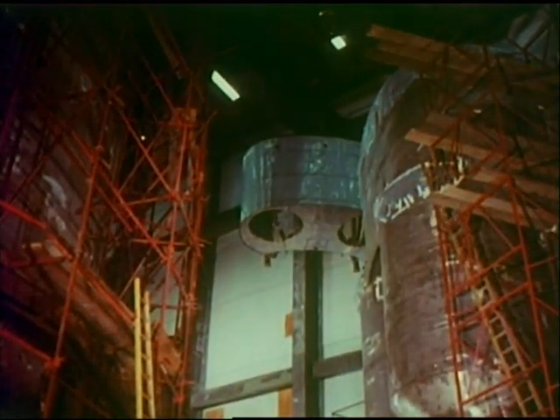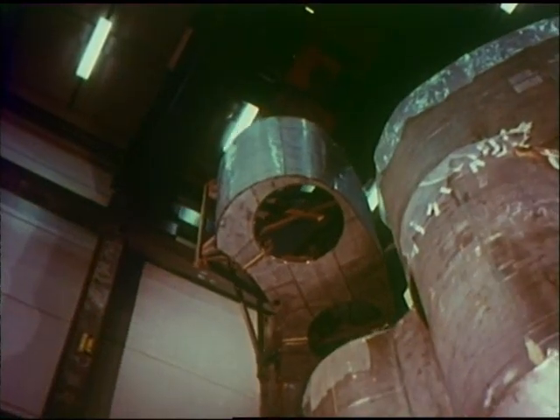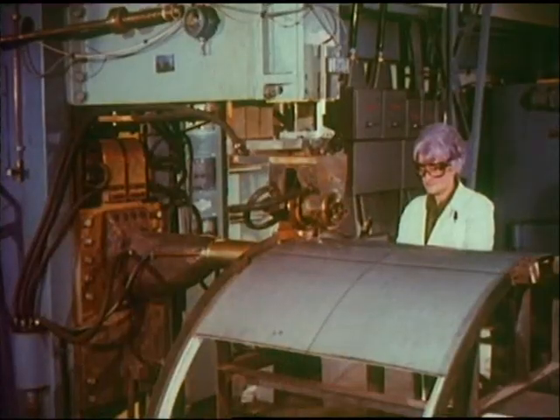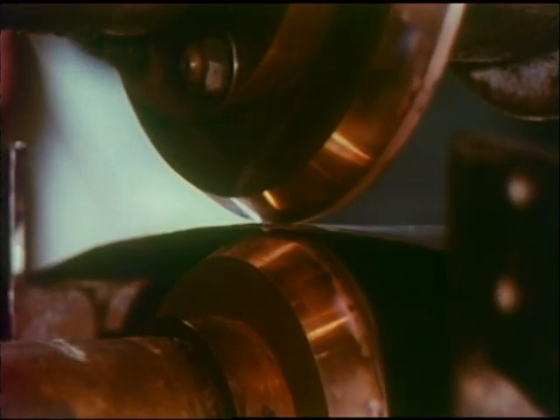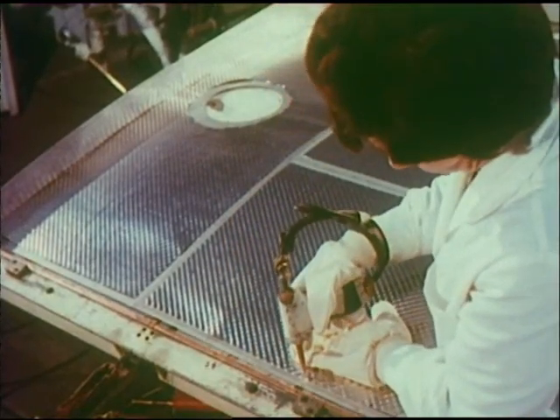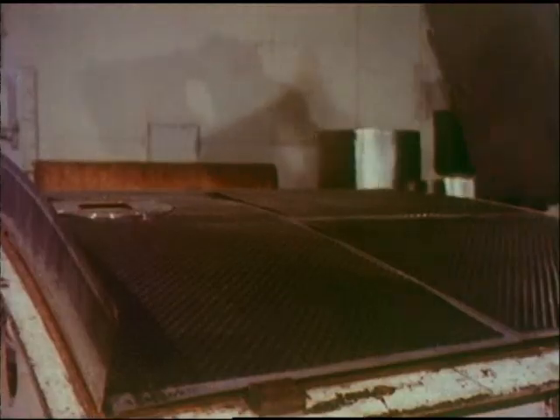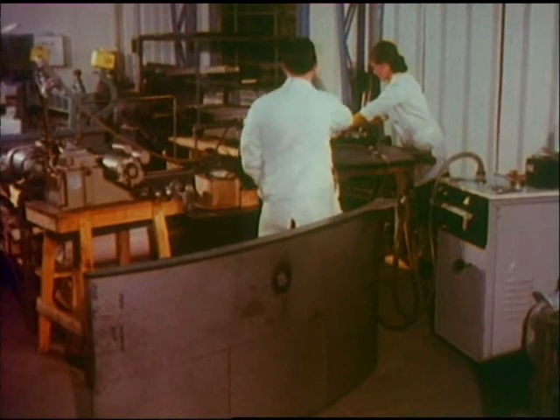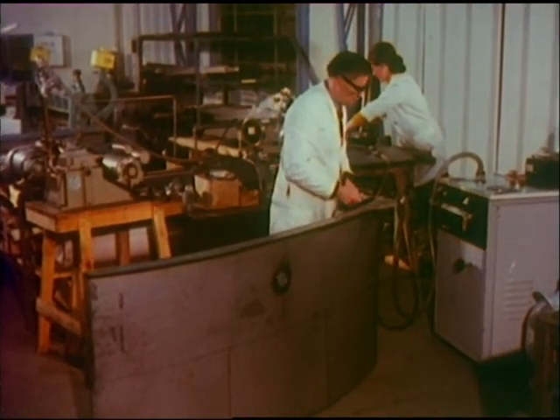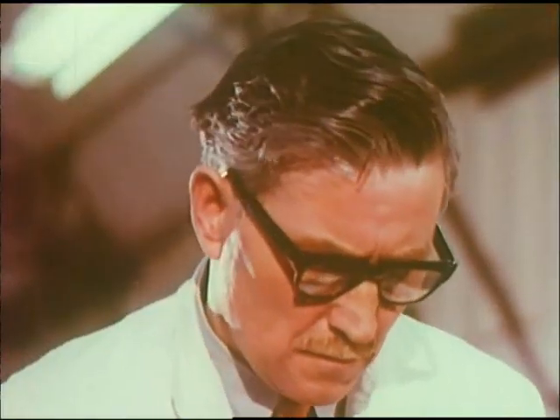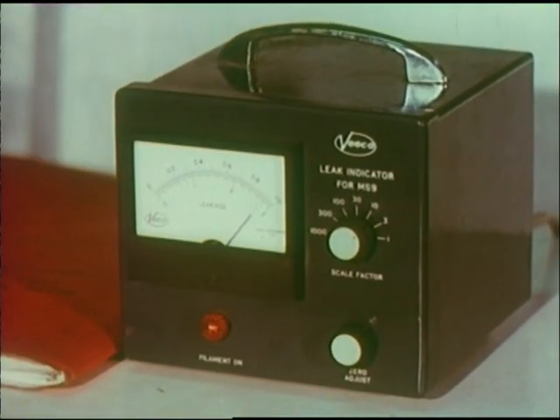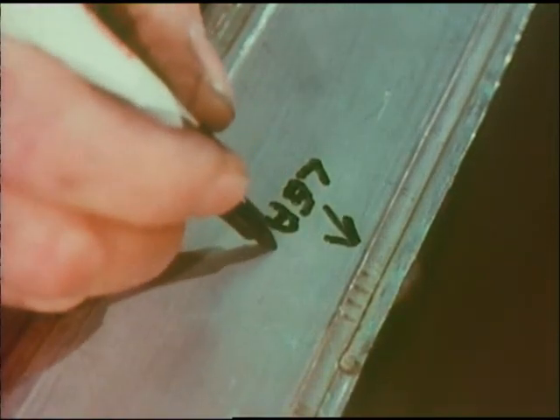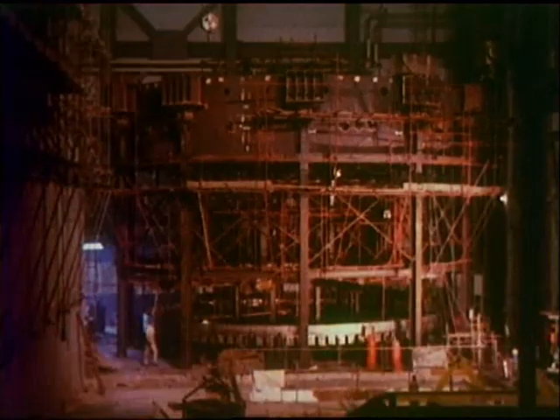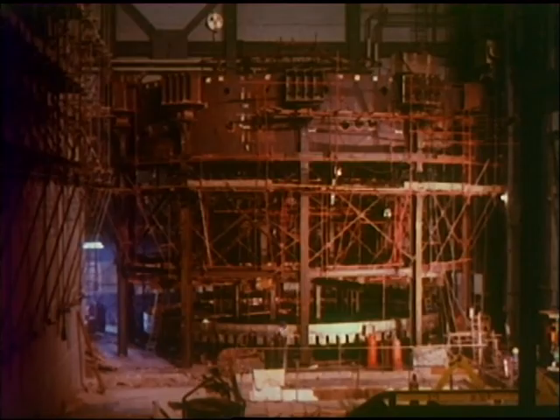As the purpose of the reactor jacket was to separate the hotter from the cooler zones of sodium in the pool, thermal insulation was required. Insulation panels were made up of 2 stainless steel sheets with spaces between them, seam welded round the edges and at intervals to form closed pockets of argon gas. After fabrication, every panel was tested for leakage by mass spectrometer. The attachment of these insulation panels to the reactor jacket was carried out in the reactor hall, 4 layers of the panels being applied.